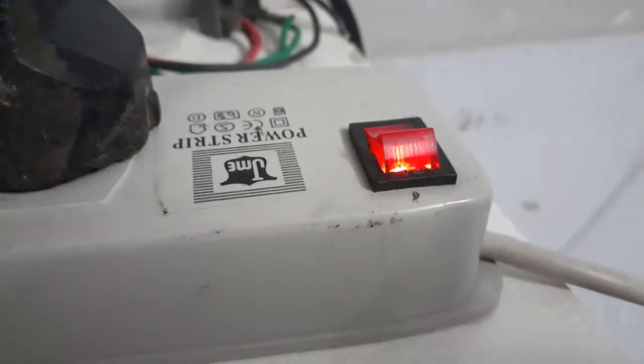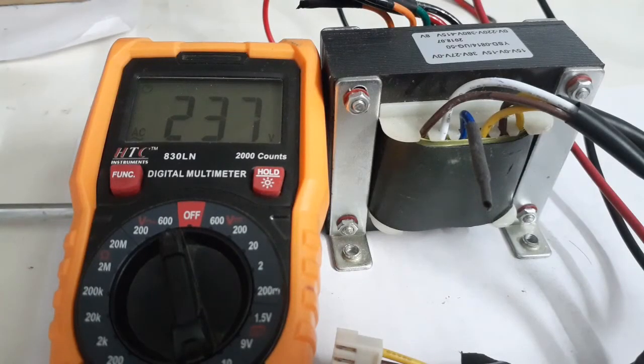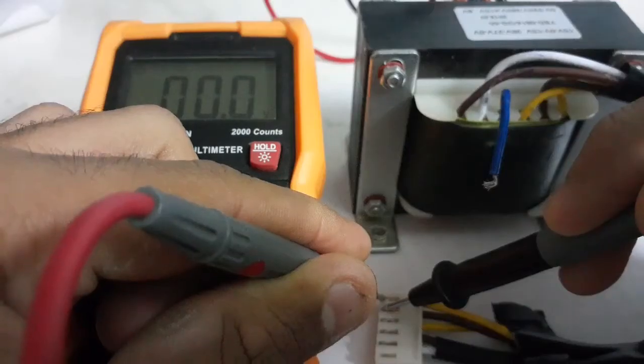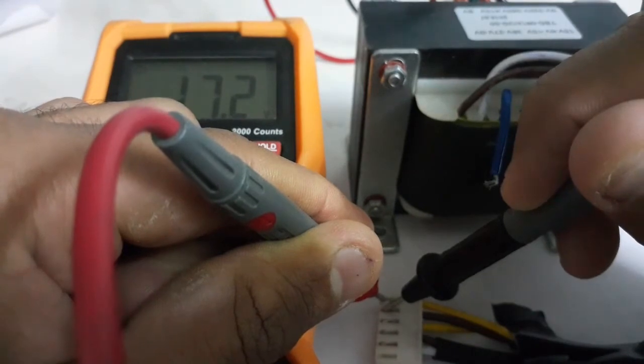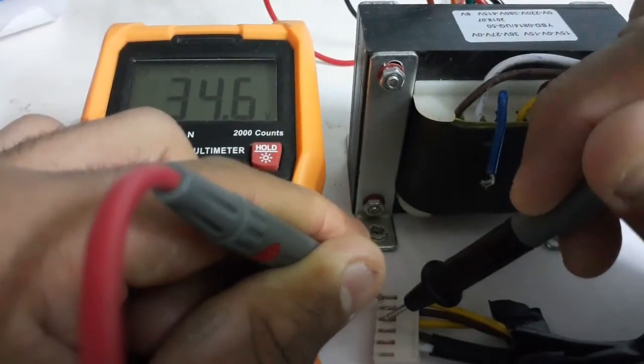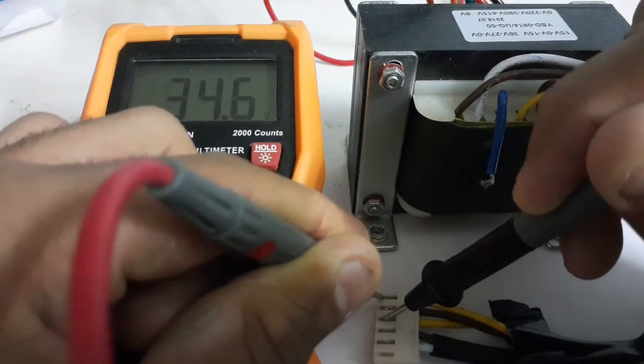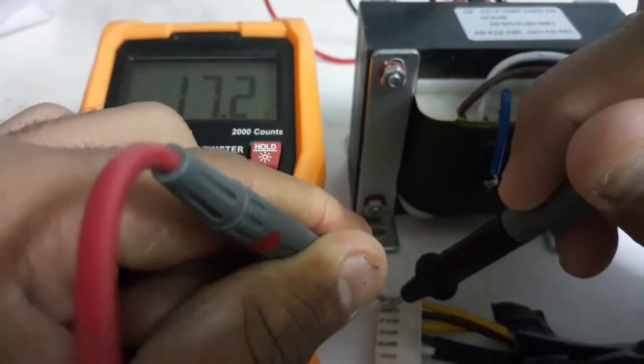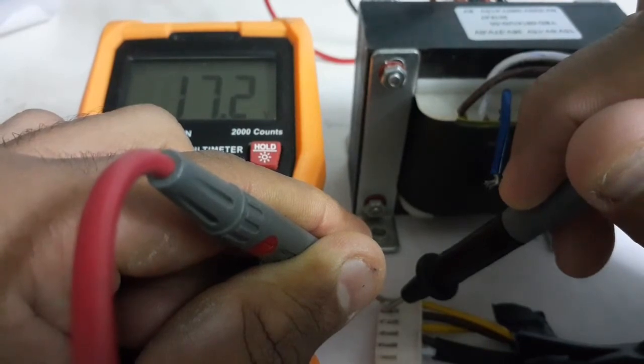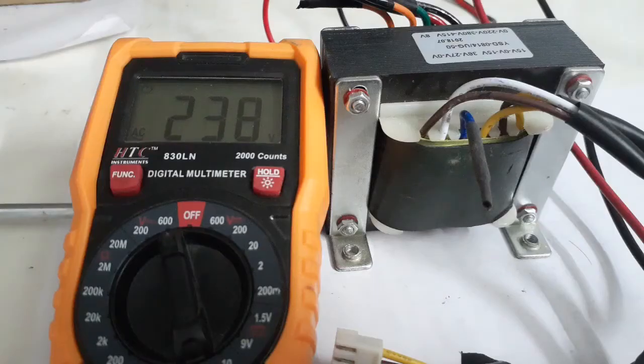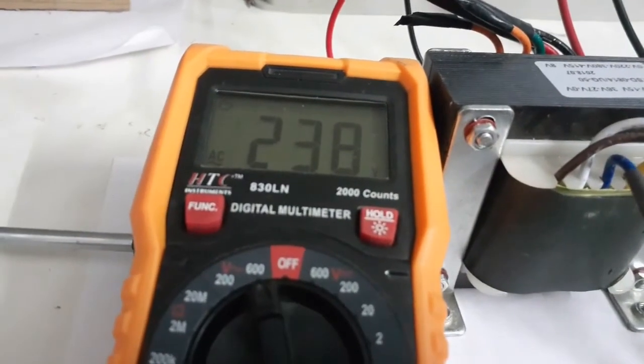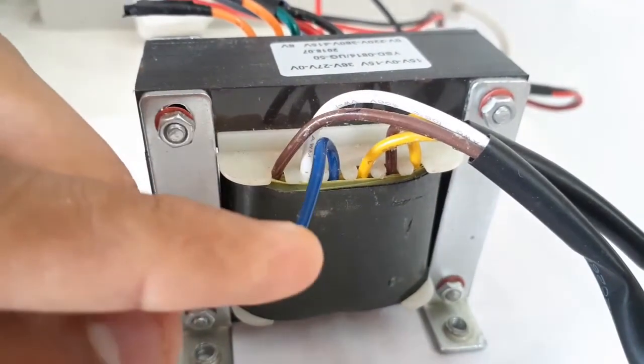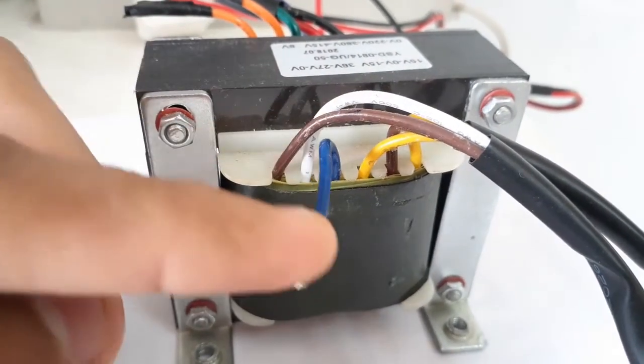The main purpose is to step down voltage, for example from 230-volt mains to 17.5 volts or 34 volts. This is called bucking of voltage. They also boost voltage, which means step up, for example from 17 volts to 230 volts.